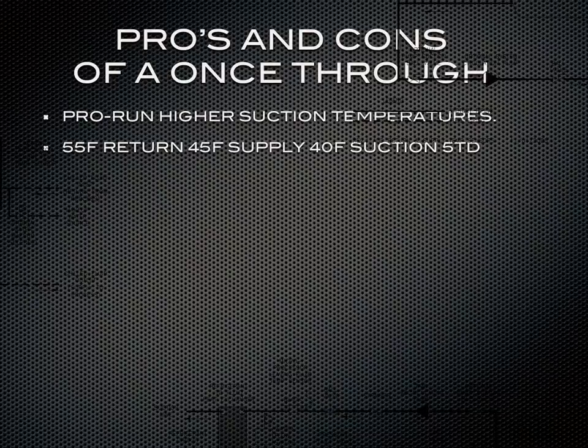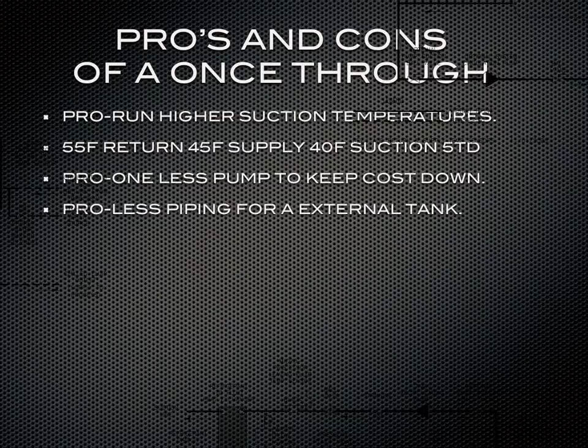On a recirc setup, you're going to have around an 8 to 10 degree temperature difference, and that chiller is going to have less capacity on it. I can really do a whole video on this. Another pro is that there's one less pump, and that will keep costs down. The same goes for piping on an external tank. Kind of goes for an internal tank too. If you have less piping, that will keep costs down.